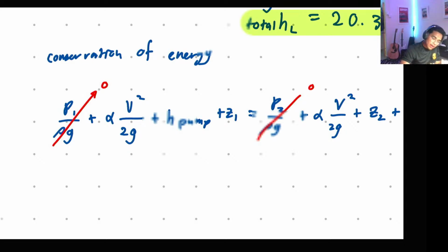The power is pressure times flow rate. Betul? Betul. The flow rate is 0.01. So 228.52 kilopascal times 0.01 meter cube per second. Betul. So dapatlah W is equals to 2.285 kilowatt. But there is a but.